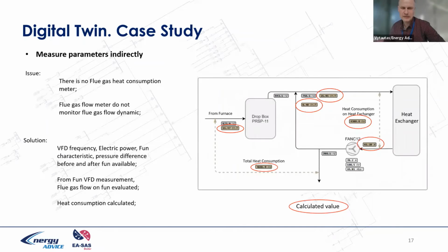Another project with a digital twin shows the difference from a SCADA system, which can do measurements indirectly. For example, in this case, the client had the issue of calculating the flue gas thermal energy consumption for the heat exchanger. In the scheme, we have gas from the furnace and a drop box for ash collection. We had a fan for recirculation, temperature adaptation, and outgoing flue gas. We have data from the fan: frequency from the variable frequency drive, active power, and pressure drop in millibar.